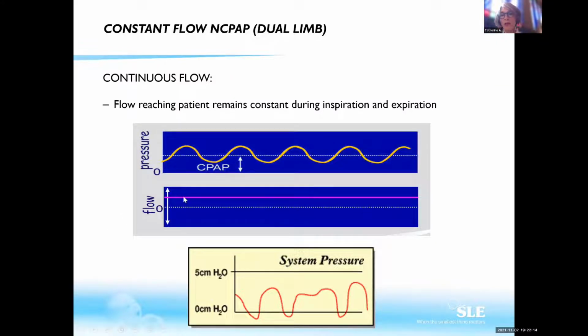If I look at the flow, what you see here is that the flow is very constant. It doesn't change. But during my inspiration, for example, you will see that the CPAP is decreasing a little bit, which is normal because the patient is generating a negative pressure. And when the patient is exhaling, because he's exhaling against the flow, you will see that the pressure will be increasing. So you will see some fluctuation here on the CPAP.